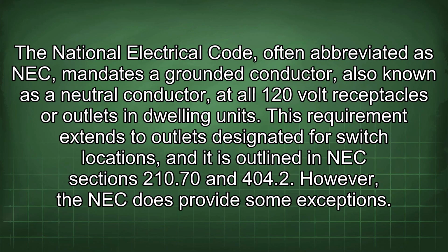The National Electrical Code, often abbreviated as NEC, mandates a grounded conductor, also known as a neutral conductor, at all 120-volt receptacles or outlets in dwelling units. This requirement extends to outlets designated for switch locations, and it is outlined in NEC sections 210.70 and 404.2. However, the NEC does provide some exceptions.